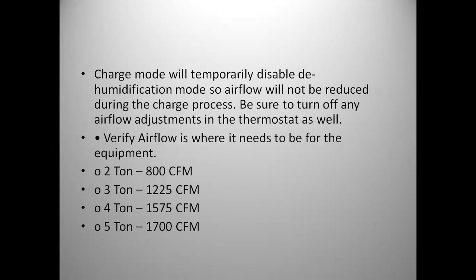Now with the EcoNet, they have what they call a charge mode. So on the EcoNet, you'll see a feature that says ODU checkout, which is outdoor unit checkout. You'll have low heat, high heat. You'll also have charge heat and charge cool. So depending on which one you're trying to do, either charge heat or charge cool, you will go into charge mode, and it will temporarily disable dehumidification and turn off any airflow adjustments. Also, it's going to immediately put it into high stage, so there's not a whole lot of waiting period. Within a couple minutes, you will be at the appropriate RPMs.